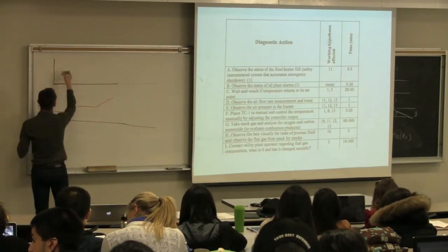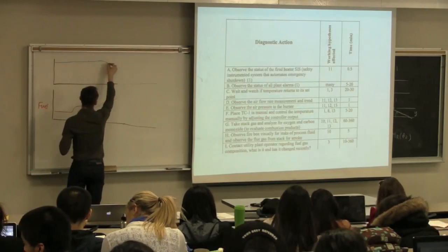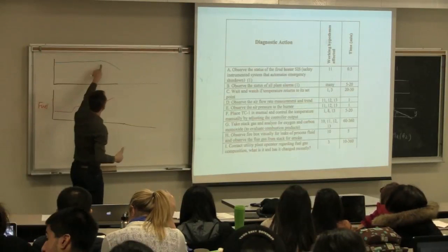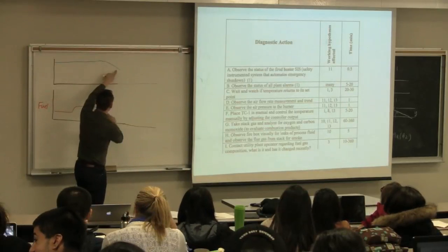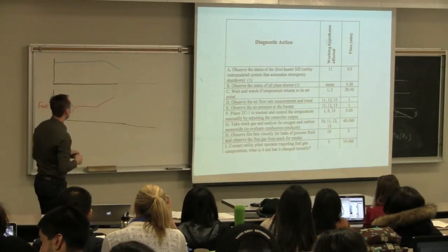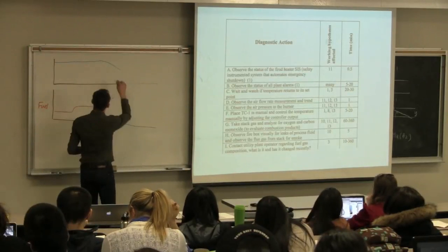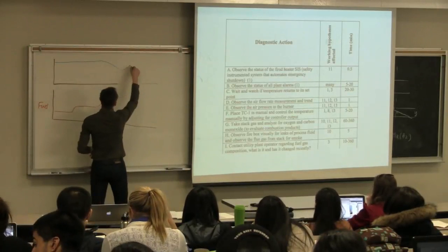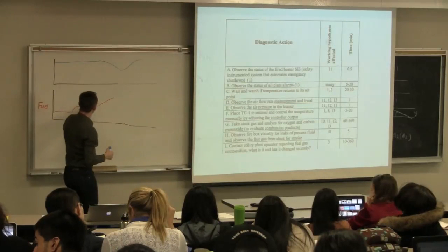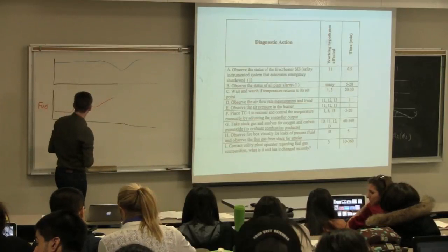So the initial part is that temperature flat line, and then it started to drop off. The fact that temperature is dropping off and fuel is going up, that's our normal expectation based on feedback control. But what we expect to see and what hasn't happened is that we expect this to go back up again, so that this increased amount of fuel will heat up that temperature. Okay?